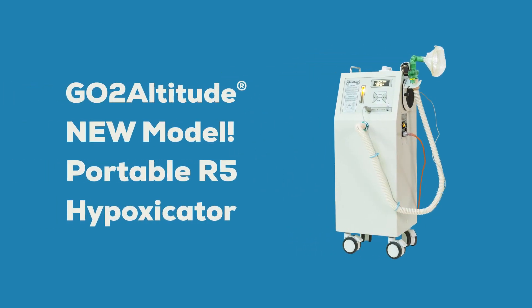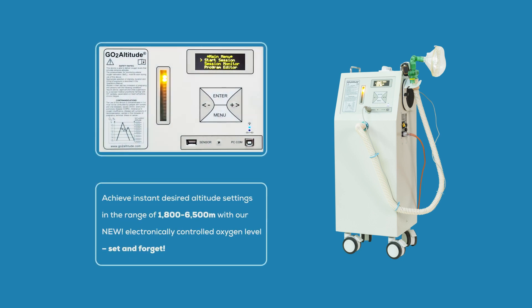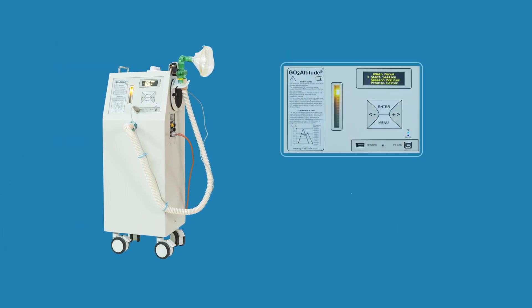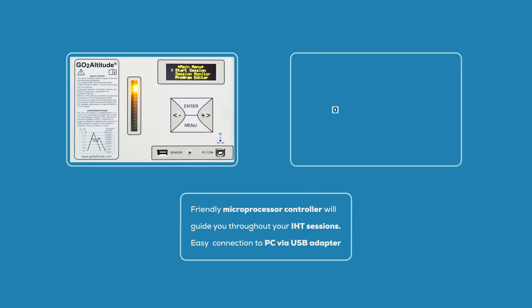Introducing the GO2Altitude new model R5 portable hypoxicator. Easily set your desired altitude within the range of 1800 to 6500 meters by simply dialing in your target simulated altitude. The desired altitude is controlled and accurately maintained by electronics. A user-friendly microprocessor controller guides you throughout your IHT sessions.